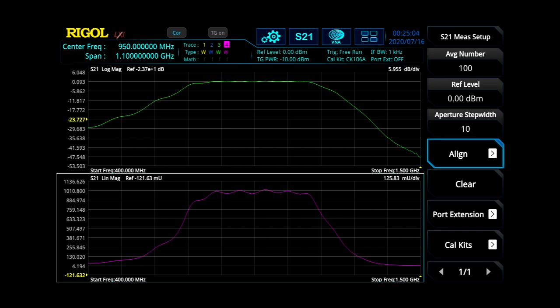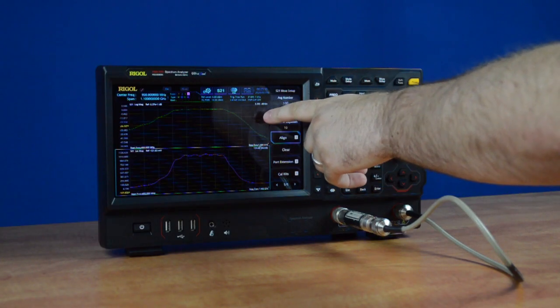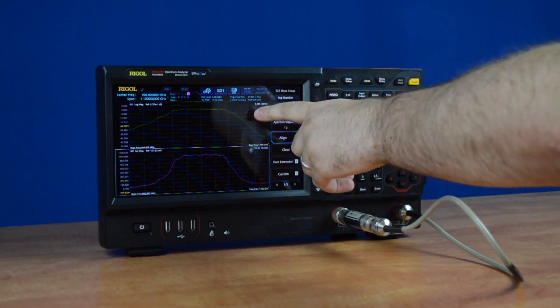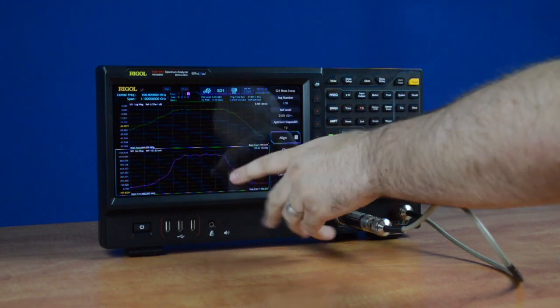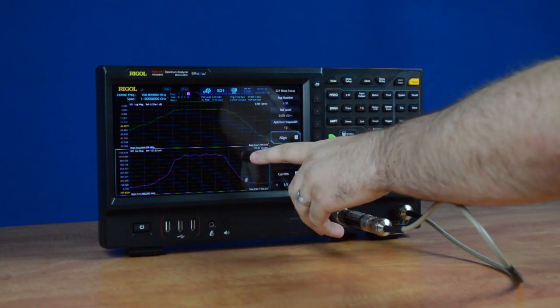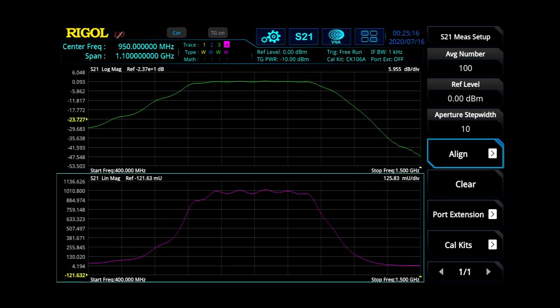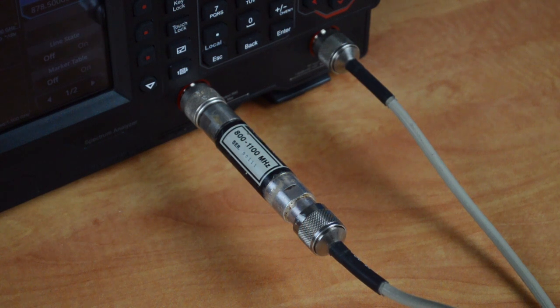I've already gone ahead and pre-configured our instrument to set its frequency range and span to show our S21 measurements. On our top display we've got our log base magnitude, and then we've got our linear magnitude displayed below. The instrument is also calibrated for S21 measurements, and our bandpass filter is already pre-attached.